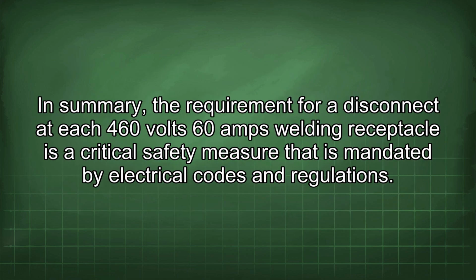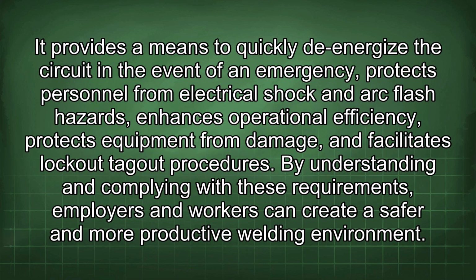In summary, the requirement for a disconnect at each 460 volts 60 amps welding receptacle is a critical safety measure that is mandated by electrical codes and regulations. It provides a means to quickly de-energize the circuit in the event of an emergency, protects personnel from electrical shock and arc flash hazards, enhances operational efficiency, protects equipment from damage, and facilitates lockout-tagout procedures. By understanding and complying with these requirements, employers and workers can create a safer and more productive welding environment.